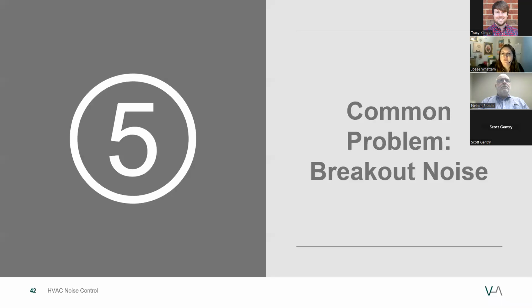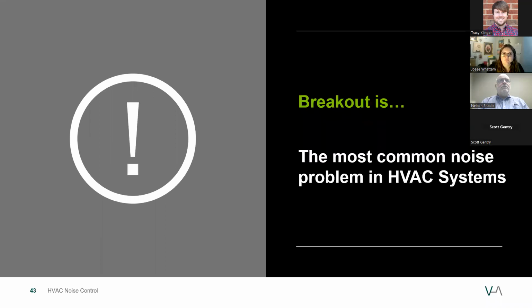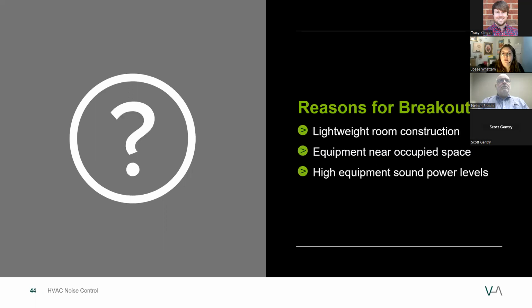Okay, so after speaking about some noise paths, I want to concentrate on breakout noise for a few minutes. Breakout is unquestionably the most common noise problem that is missed at the design stage. These are the reasons that a breakout noise problem could occur. Number one would be lightweight construction of the structure, allowing noise to permeate between spaces. Number two would be packaged equipment like AHUs and RTUs being installed near occupied spaces. Number three, high sound power levels due to higher RPMs or compressors.